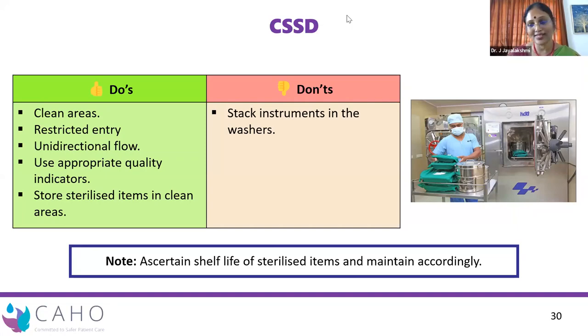So that's about CSSD, right? Okay, there is something about identifying the shelf life of the sterilized material. It so much depends on what sterilization process you're doing, and also what packing material you've used. Then accordingly, if you have validated the process in your own settings and seen that they are remaining sterile for a number of days, that's the best way to go ahead and identify a date. And it is good to see whether your expiry dates are captured on the material, and you are not using or keeping any of this material which is beyond expiry in any clinical area in the hospital.